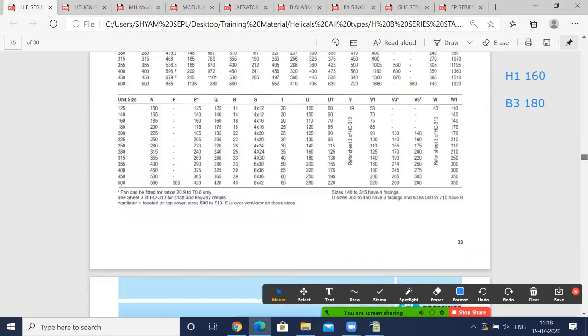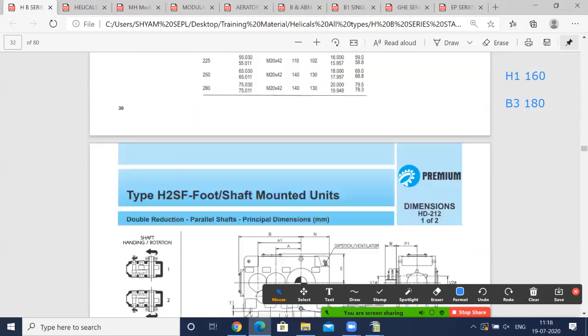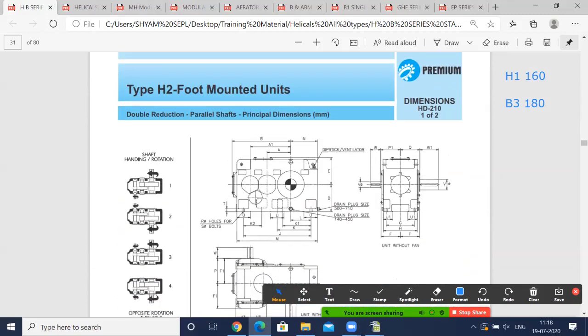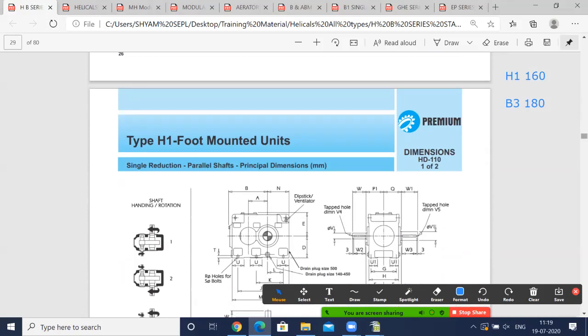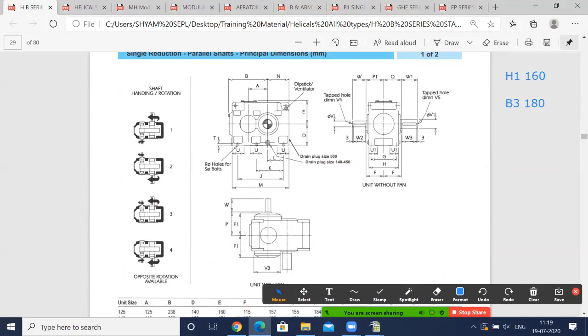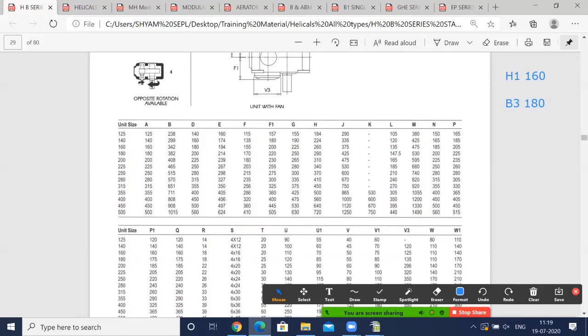Okay, so what two models did we select today? One was H1, let me write it down here: H1 160 and the other was B3 180. Let us see these two models in the catalog drawings, how the size came into the picture. First I'm opening H1. Here is the H1. This is the top view. This is the input shaft, this is the output shaft, and this distance from input to output is known as A. So A is your center distance in this case. The center distance is the size of the gearbox. You can see unit size and A are the same.